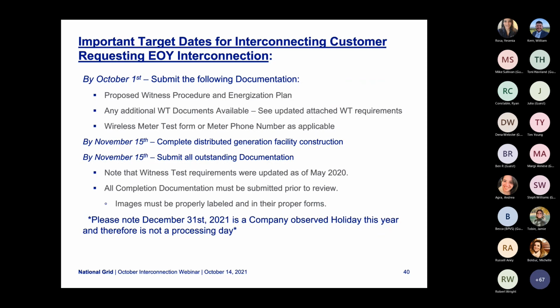Please keep in mind that the company will not issue ATI until the interconnecting customer has satisfied all interconnection requirements, such as wiring inspections, compliance documentation, the witness test, ISO-NE registration, and the company meter is installed. Additional information can be found in the link below. And again, don't hesitate to reach out to your account manager. Thank you.